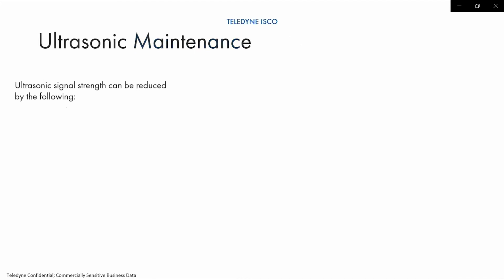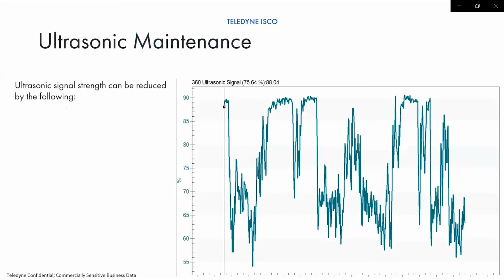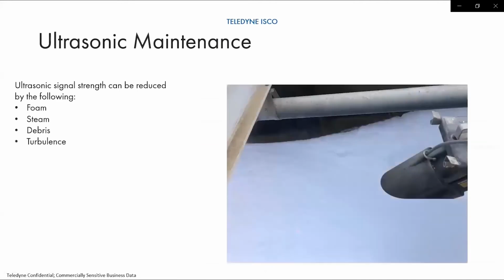Now, as far as the ultrasonic sensors, we'll stick with that for a little bit. What we're looking at here on this graph is the ultrasonic signal strength, and it's all over the place. Normally with the ISCO equipment, your ultrasonic signal should be at around 90% or higher. When you start seeing something like this, where the signal's going up and down, you have to start asking yourself what's causing the problem. Are you having issues with steam or foam or debris going through there? It's not necessarily an issue with the sensor, but could be more the application. Like with this foam, they ended up putting sprayers up front to knock down the foam, and that took care of the issue. If you had a lot of steam, that could also cause a problem.